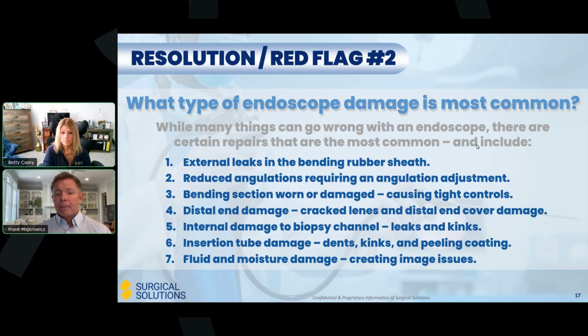Very common there. And then the last two, insertion tube damage. That would be external damage, whether something was run over by a cart, closed accidentally in a door, the lid of the scope reprocessor pressed up against it, or maybe in an upper endoscopic procedure, the bite block fell out of the patient and they clamped down on the tube. So we see a lot of tubes come in that are kinked and dented and damaged as well.